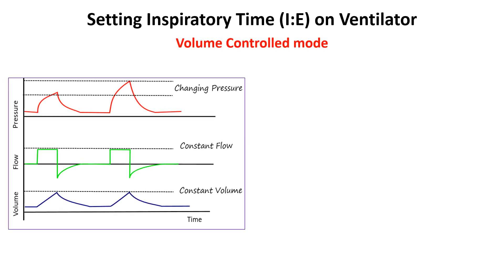Let's start with volume control mode. Volume-controlled ventilation is a mode of mechanical ventilation in which the ventilator delivers a preset constant tidal volume to the patient during each breath. Since the ventilator delivers a fixed tidal volume, the inspiratory time depends on how fast or slow that volume is delivered at a certain flow rate. To quantify the relationship between flow rate, tidal volume, and inspiratory time, we use this formula.